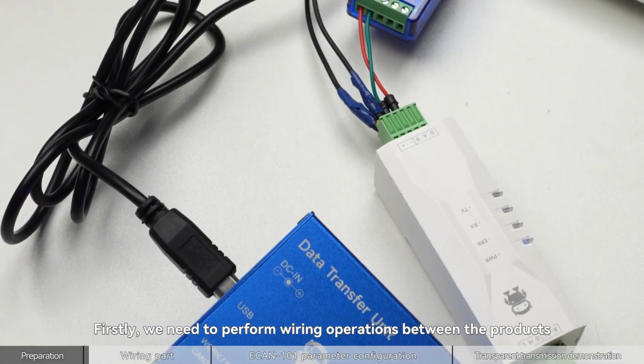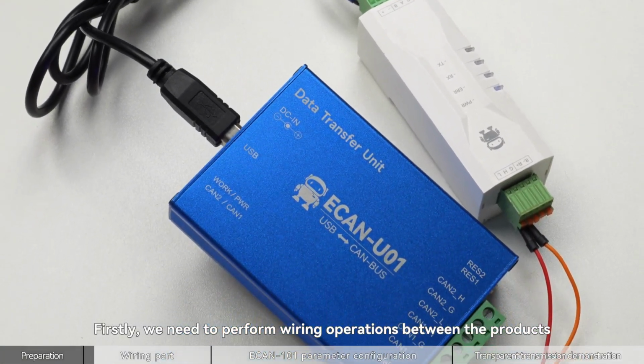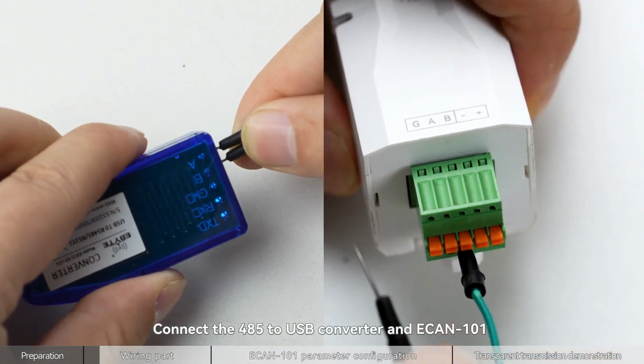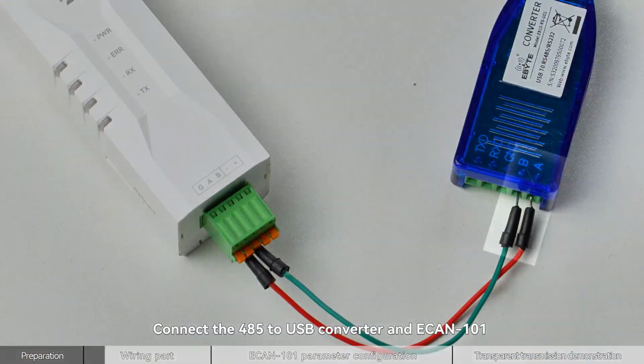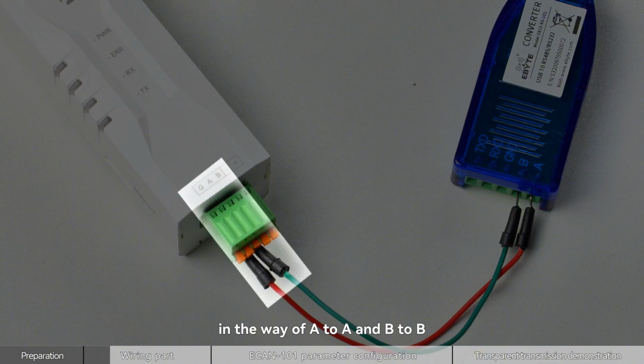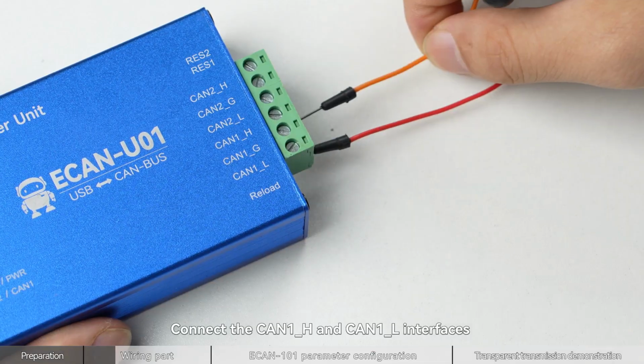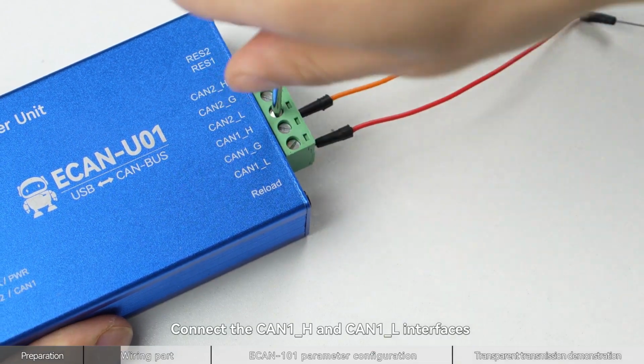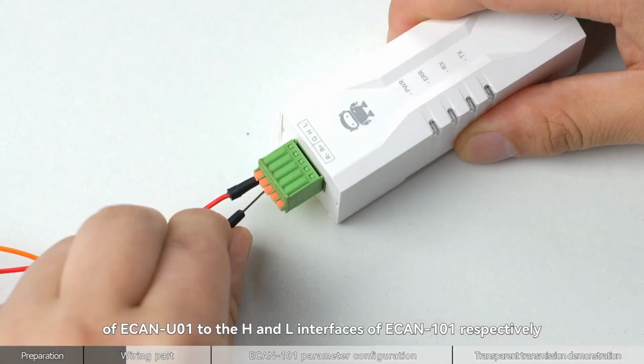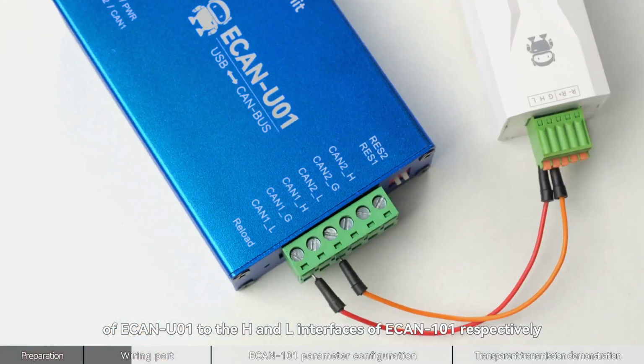Firstly, we need to perform wiring operations between the products. Connect the 485 to USB converter and ECAN-101 in the way of A to A and B to B. Connect the CAN-1H and CAN-1L interfaces of ECAN-U01 to the H and L interfaces respectively.